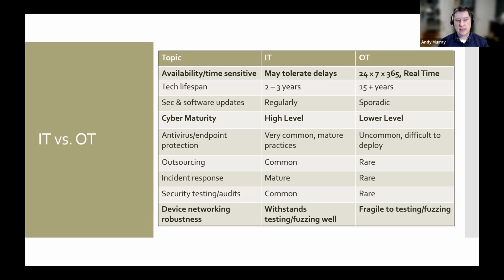The other reason is SCADA systems, for all their great use and how much utilities rely on them, utilities will have the ability to run their system without SCADA at any time. They have manual controls for everything SCADA does. The one thing they might lose is their data analysis, but you can go down and write down values. They would still have meters that display those values, so that value would still be accessible at any time.